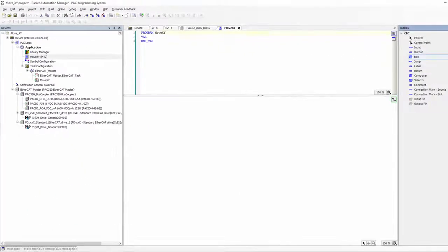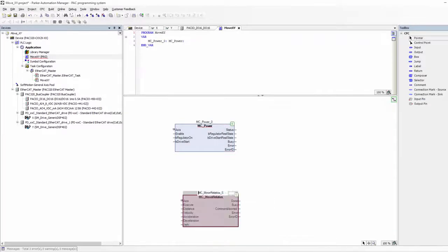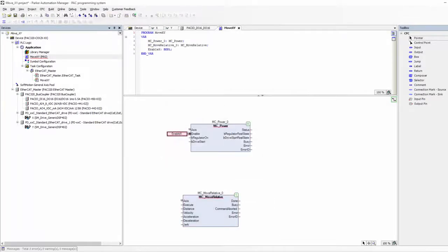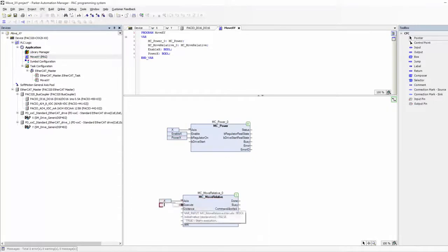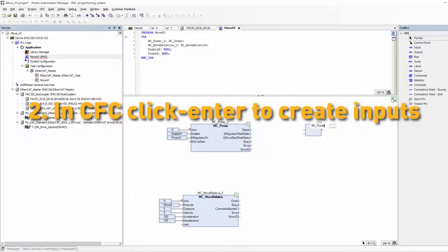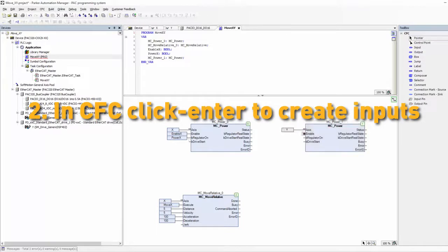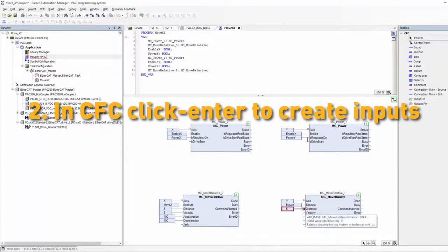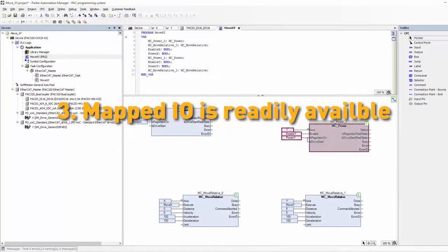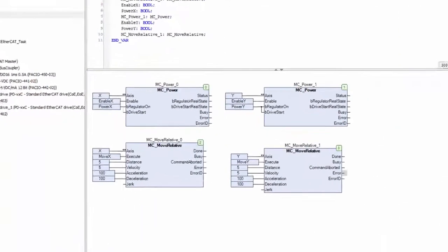Here I am doing some exponentially fast programming in continuous function chart. Note, I'm allowing a few things to happen here that is speeding up my programming significantly. I'm allowing Automation Manager to auto declare all of my function blocks and my variables. Since I'm creating my inputs by clicking on the desired input of the function block and pressing enter, Automation Manager already knows the appropriate data type that I'm trying to create. In addition, all of my axis and PAC I/O are global variables so I can use them directly in my program.